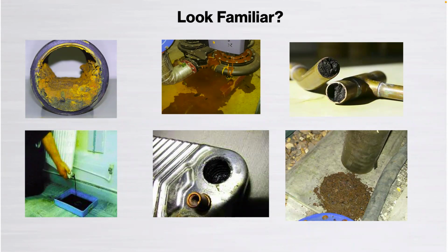In terms of CapEx, not just OpEx cost of energy and so forth, but CapEx costs and life cycle, we could be replacing radiators much sooner than we should be. Time and time again, I hear and I see from estates technicians, universities and hospitals, there's a huge amount of inefficiency of their time where they're constantly being called out on the radio because they've got leaks and they need to go and sort a leak out and then go and get a new radiator and change it because they've had pinholing failures.